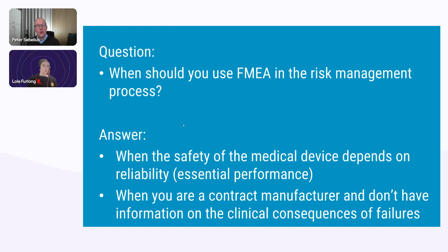One should keep in mind that ISO 14971 requires you to look at combinations of events, not just single faults. And FMEA is a single fault technique. It will only look at one error and what that will lead to, but we are required to take a broader approach and look at combinations, which is important. So I recommend taking a look at that. The FMEA article, I believe we can link here in the webinar. When it comes to this article series, The Danger of Division, as I call it, there will be a link sent to you after the webinar where there's more to read on that, if you're interested.